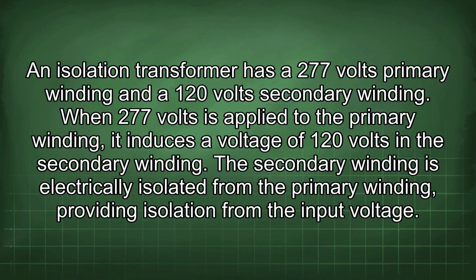An isolation transformer has a 277 volts primary winding and a 120 volt secondary winding. When 277 volts is applied to the primary winding, it induces a voltage of 120 volts in the secondary winding. The secondary winding is electrically isolated from the primary winding, providing isolation from the input voltage.